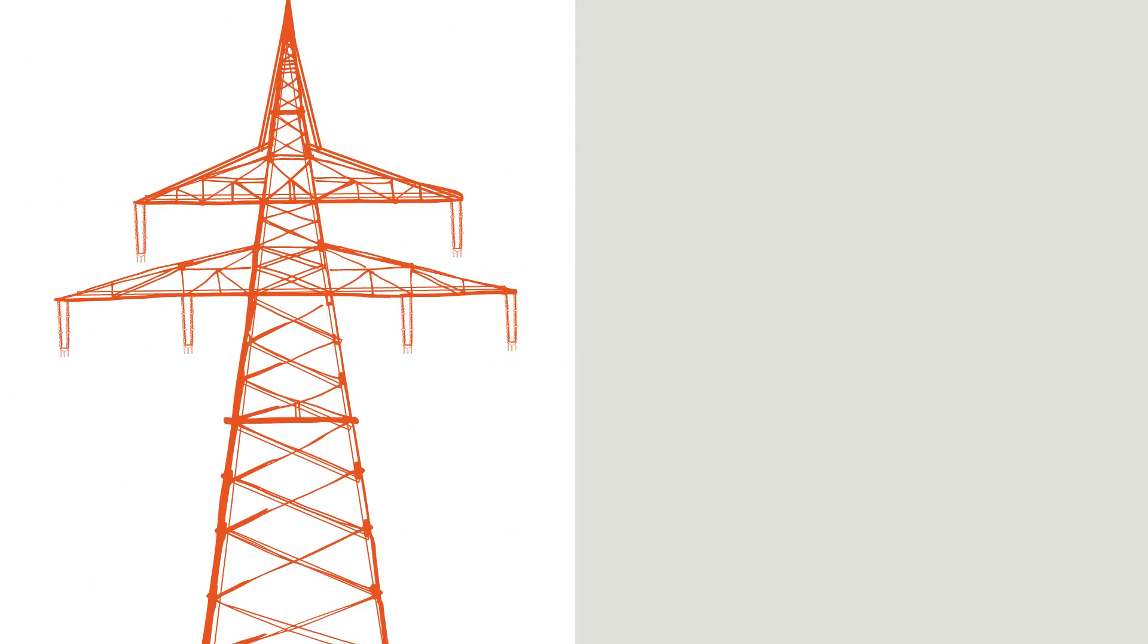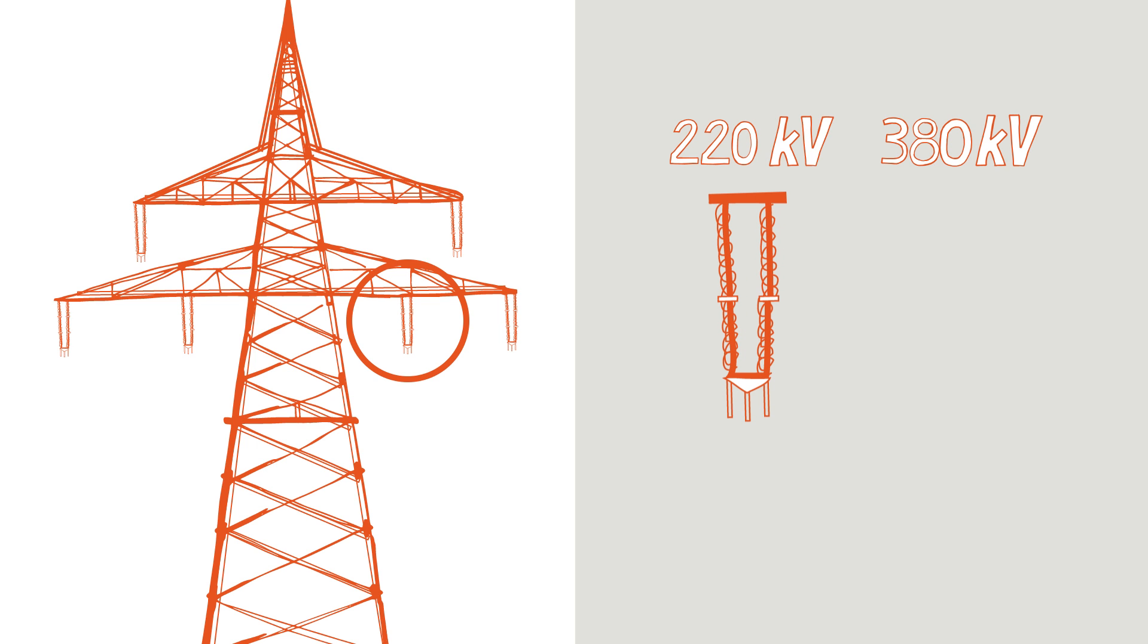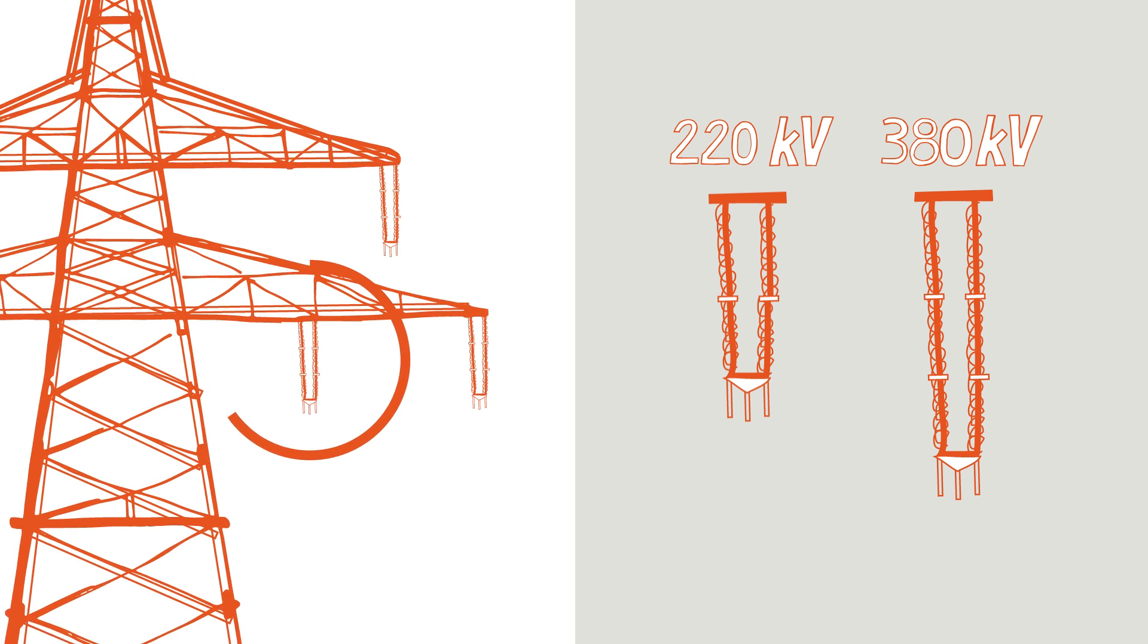Conductors have to be isolated from the earth and pylon. They are therefore fixed with isolators. Normally, the difference between 220 and 380 kilovolt lines can be pinpointed by checking the number of isolators. 220 kilovolt lines frequently have two, 380 kilovolt lines three or four isolators.